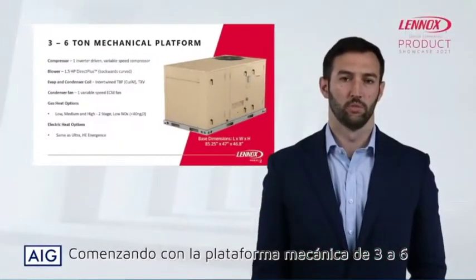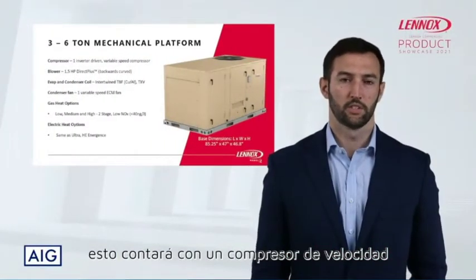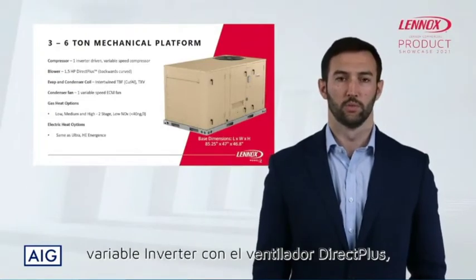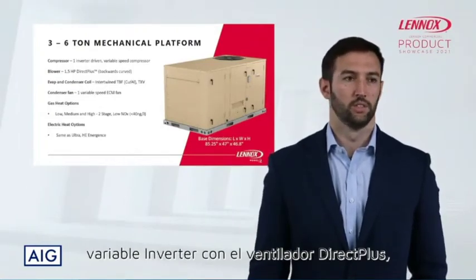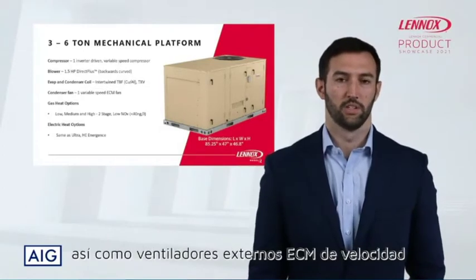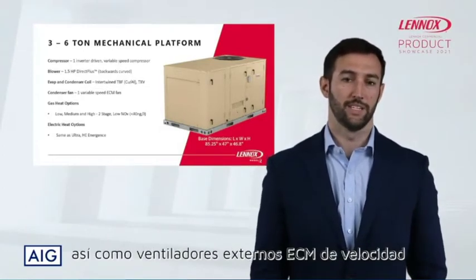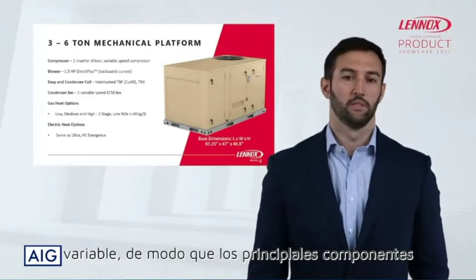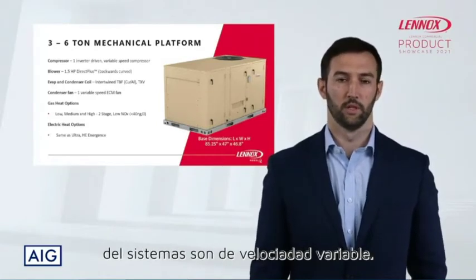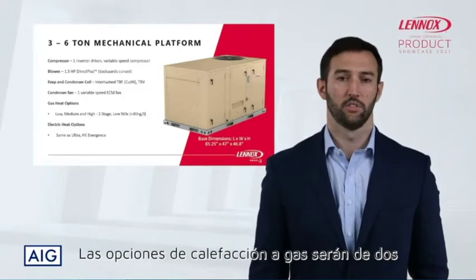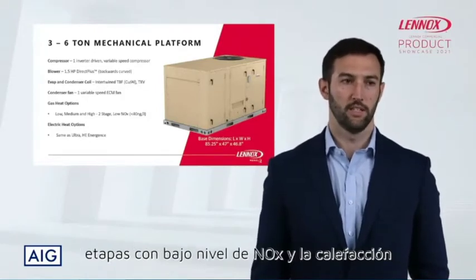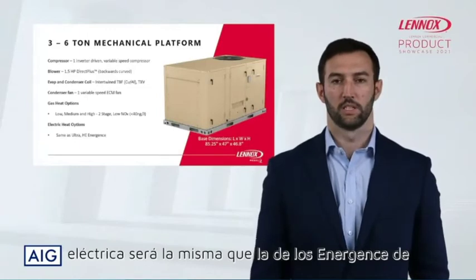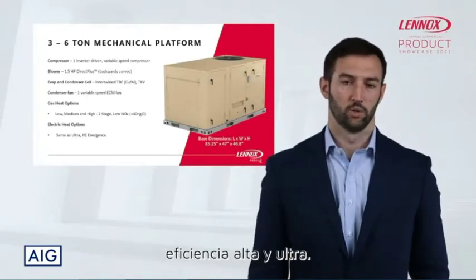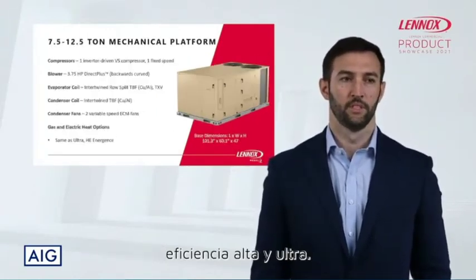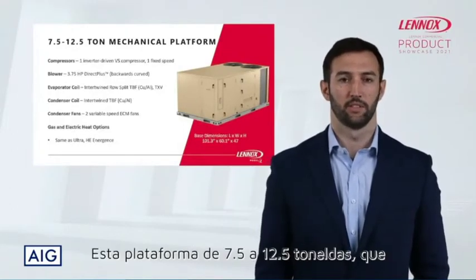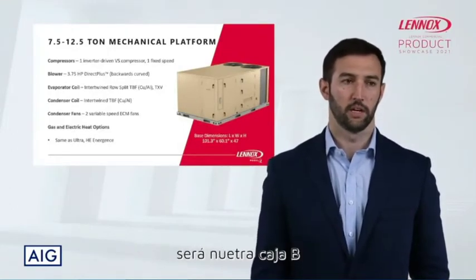So starting with the 3 through 6 ton mechanical platform, this is going to feature one inverter-driven variable speed compressor with the direct plus blower, as well as variable speed outdoor ECM fans, so that all main components of this system will be fully variable speed. The gas heat options are going to be two-stage low NOx gas heat, and the electric heat is going to be the same as Energence high efficiency and ultra. Looking at the 7.5 through 12.5 ton platform, this is going to be our B-box.